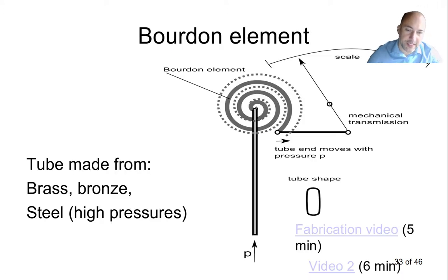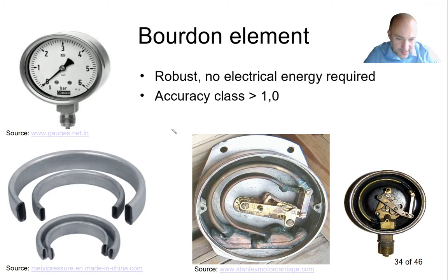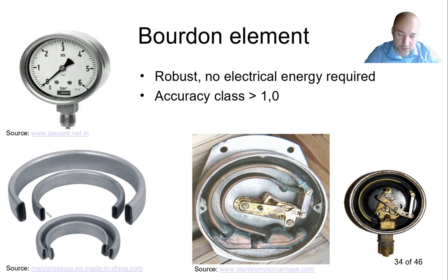The first device is quite often used — the Bourdon element pressure gauge. Looking at photographs, we can see a Bourdon element here. The Bourdon element is nothing else than a tube that has been flattened, and this tube changes its shape with pressure. We connect the measured pressure on one side of the tube. The other end is sealed, and if the internal pressure increases the Bourdon tube tries to straighten itself. We detect this change of shape.